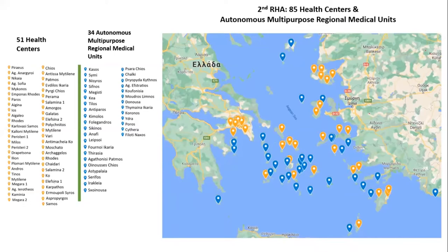Even though the health center names may sound enjoyable to many of you — perhaps reminding you of a vacation in Greece — to us, these special geographic characteristics were a challenge. For this reason, a working group of nine experienced biomedical engineers was created and a straightforward, well-defined protocol was developed for the registration procedure. The whole region was divided into sectors, and each biomedical engineer visited every sector — island by island, municipality by municipality, health center by health center, and room by room — registering every electrical medical device.